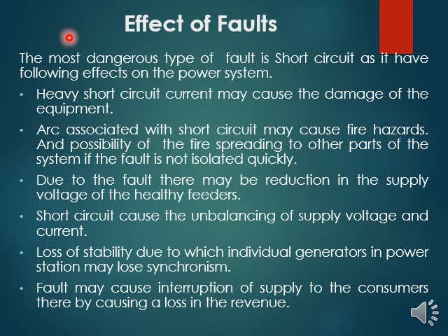Effects of faults. The most dangerous type of fault is the short circuit, as it has the following effects on the power system. The heavy short circuit current may cause damage to the equipment. The arc associated with the short circuit may cause a fire hazard, and the possibility of the fire spreading to other parts of the system if the fault is not isolated quickly. Due to the fault, there may be a reduction in the supply voltage of the healthy feeder. Short circuit causes unbalancing of supply voltage and current.